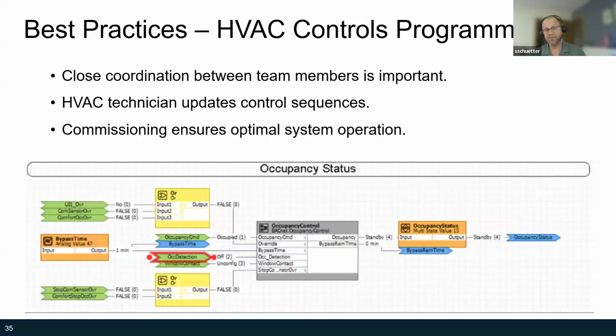During integration, facility IT staff, the lighting control commissioning technician, and the HVAC control contractor will need to work together closely to discuss and resolve network integration issues. Once the HVAC system is receiving the appropriate BACnet objects representing zone occupancy, the HVAC technician should be able to revise existing sequences to reflect the design intent. After the custom HVAC control programming is implemented, commissioning will ensure the system is operating correctly.